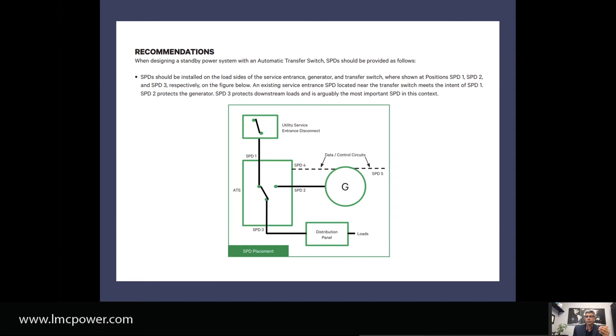It also says SPD2 protects the generator, and SPD3 protects downstream loads—arguably the most important SPD in this context. So yes, the SPD3 in their example is your category B, protecting against any transient the generator creates. But it doesn't protect the generator or the operation of the ATS itself—that's where you need your category C.